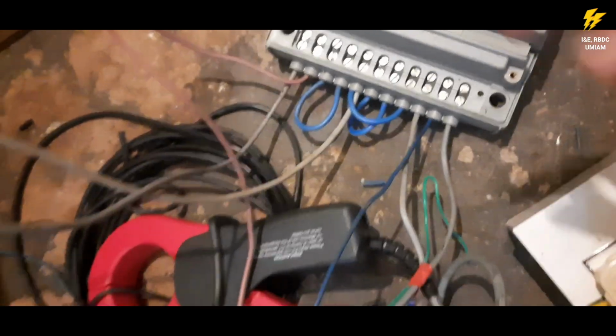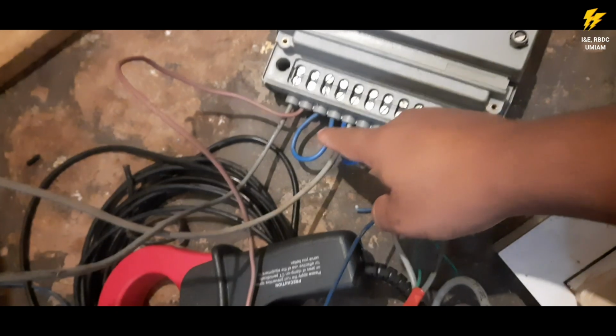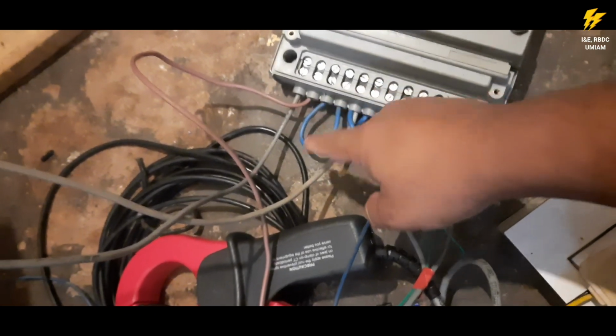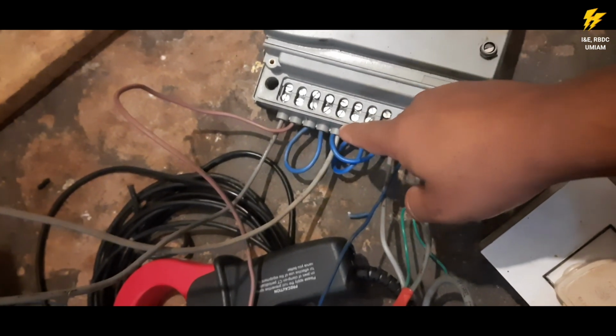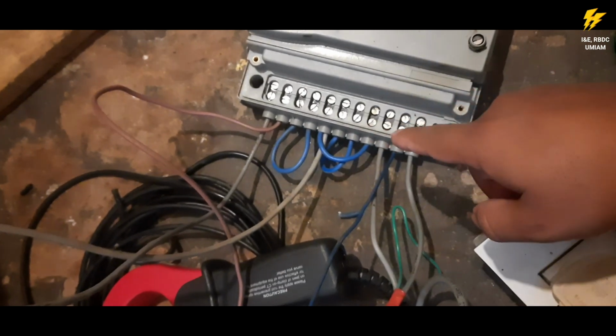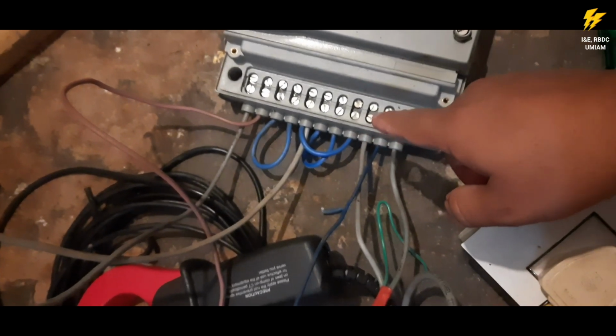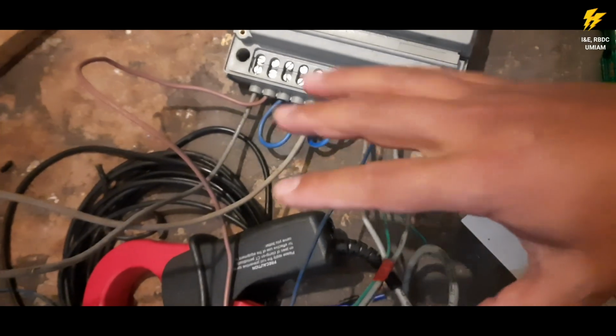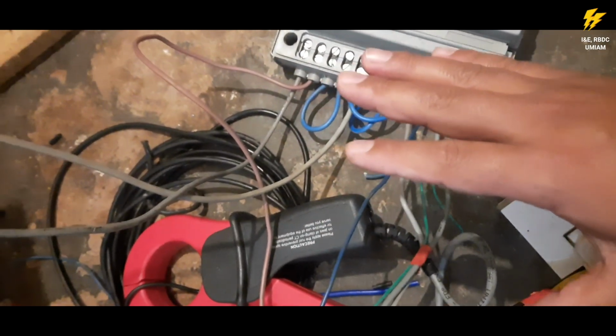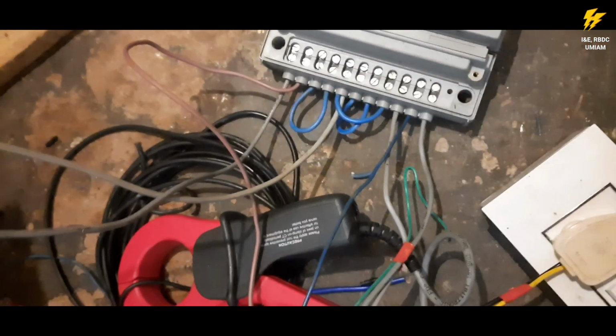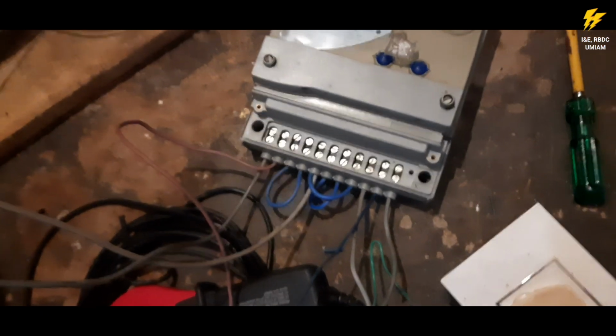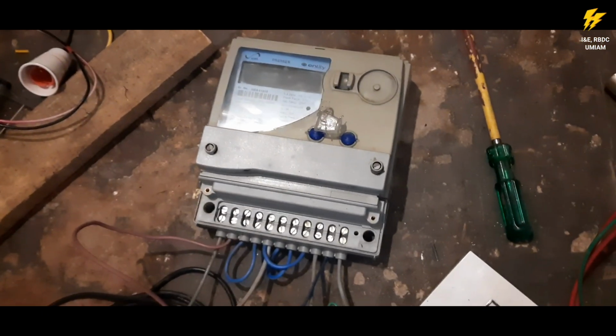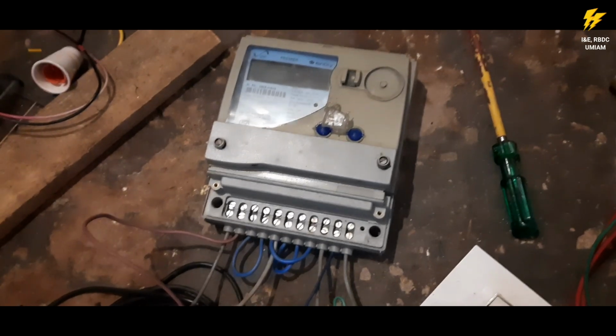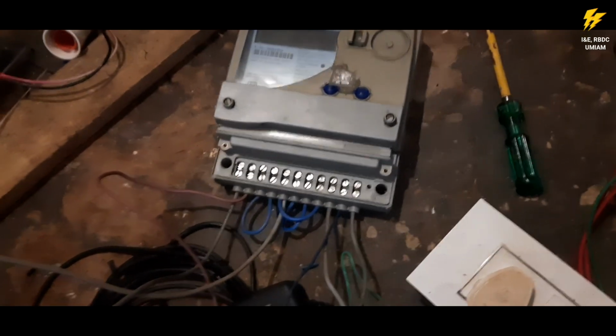It will be like whole current, and since I have only a single phase meter, I will convert this into 3-phase by looping from the R phase like this - I loop to S1 of R phase, S2, and then I loop to S1 of Y phase like this, and then I again loop to S1 of B phase like this, and then to the neutral. I'm using the same voltage to R, Y, and B - the PT supply is the same only. So in the eyes of the meter, it will be like 3-phase.